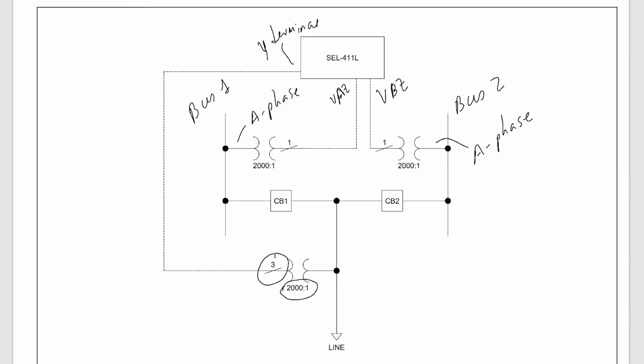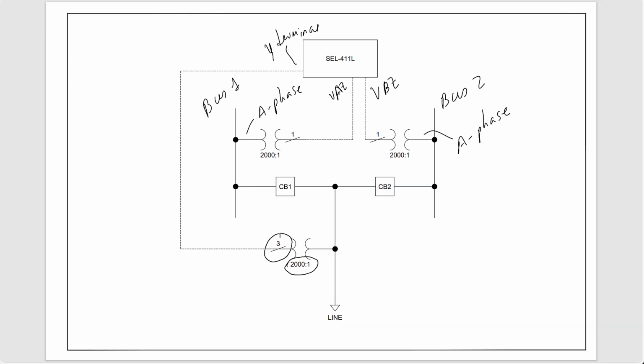So again, we have the three-phase connection from the line, that's this one over here, and we're going to use that as our reference so that we can compare the bus side voltages, but the bus side voltage that we use can be any one of the phases, or it could even be a phase-to-phase voltage. It doesn't have to be A phase. It's just that for this example, to keep things simple, we're going to use A phase, and we're also going to use the A phase for the line side voltage as the sync check voltage for the line side.